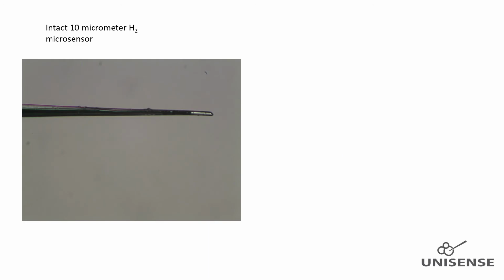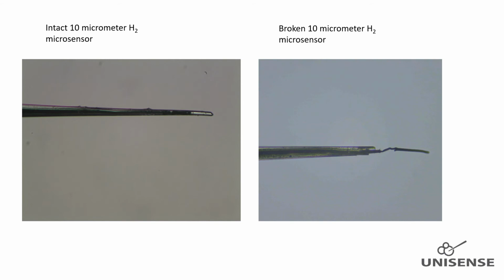I now turn to troubleshooting hydrogen microsensors, which do not exhibit normal performance. Naturally, small glass tip sensors are fragile, and the tip might break if it hits something hard. This is a photo of an intact hydrogen 10 micrometer sensor, and to the right a photo of the same sensor is shown, but now with a broken tip. It is seen how the working electrode is exposed because the glass tip is missing.